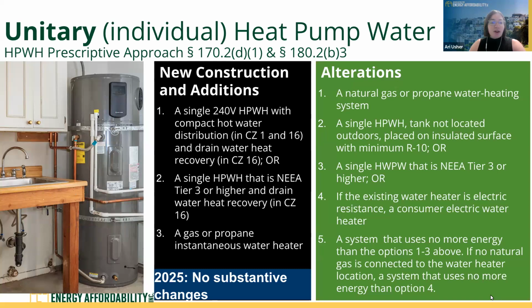For unitary heat pump water heating—your in-unit water heating—there are a couple of different options. The first is a single 240-volt heat pump water heater, with additional requirements in climate zones 1 and 16, the most extreme cold climate zones. The second option is a single heat pump water heater that is NEEA Tier 3 rated, which confirms it will perform, so you don't need those additional requirements.